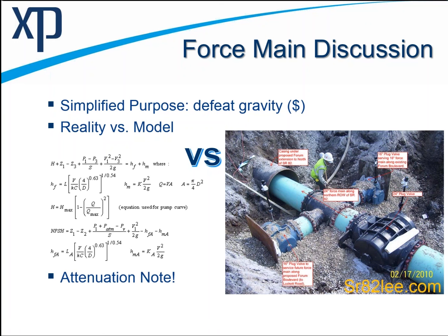And that comes in a case with attenuation. So this is something I tell people often. If you model under normal conditions and you seal all the manholes and you run this, it will be modeled in a very elegant dynamic way, which is to say you'll have attenuation and routing through your force main. Well, in the world of purely pressurized modelers, that doesn't make any sense. They assume that the pipe is completely full all the time, and if you put a drop of water in on one end, the drop of water comes out the other end. There is no real attenuation that goes through. So usually what we'll say is, I would model it the default way by sealing all the manholes, putting in your Manning's equation and running it that way. If you have actual meter data downstream and you seem to not be matching the peaks the same way the meter is, then you may consider modeling it as a special force main. And if we have time and you have interest, we'll show that in the demo here.